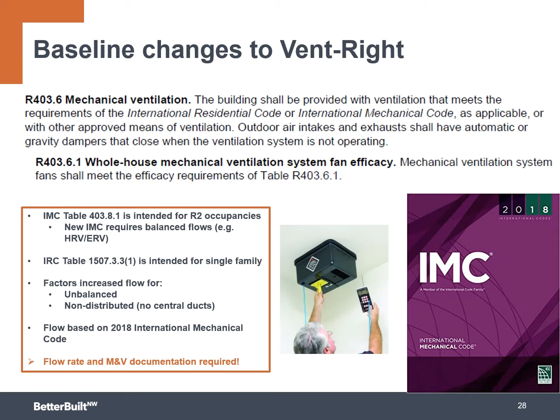So a little follow-up to the previous slide. Again, Washington State has higher necessary rates for whole house ventilation if you use an exhaust-only or a supply-only strategy. And again, the IRC that we use directs us to the International Mechanical Code as opposed to an outside standard. Again, remember with low-rise multifamily, both corridor and non-corridor versions, there's a few different new things. One is, again, that requires balanced ventilation. Another thing to note, if you're familiar with ASHRAE 62.2, 2019 is the most current and up-to-date version.